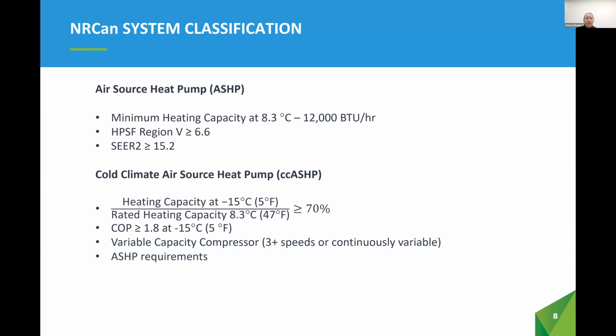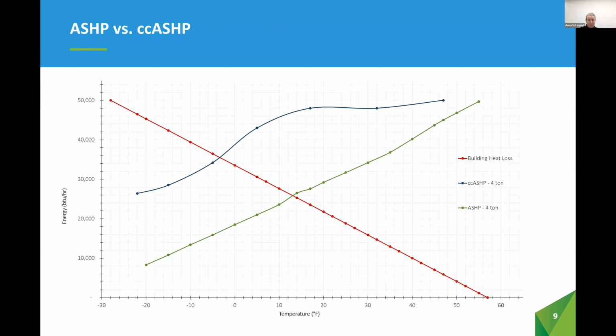What makes a cold climate air source heat pump different? Multi-stage or cascading compression systems, enhanced refrigerant control, and variable capacity compressors or fans to match unit operation with load demand. So how do these performance differences look when applied in real life? I've taken a home with a peak heat loss of 50 MBH, or 14.6 kilowatts, at a Winnipeg design day temperature, which is minus 33 degrees Celsius, and then selected 2 nominal 4-ton heat pumps to illustrate the difference between a standard air source heat pump and a cold climate air source heat pump.